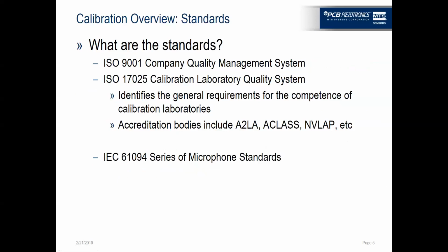Furthermore, because we're talking about calibration, because we're talking about measurement devices, ISO 17025 for calibration laboratories is another standard that needs to be followed. What that goes through is the general requirements of the competence of a calibration laboratory, and specifically it has to be accredited by either A2LA, NVLAP, ACLASS, depending on where you are in the world. One of these accreditation bodies has to come in and make sure that you're following the rules and standards of ISO 17025 if you're a calibration laboratory.